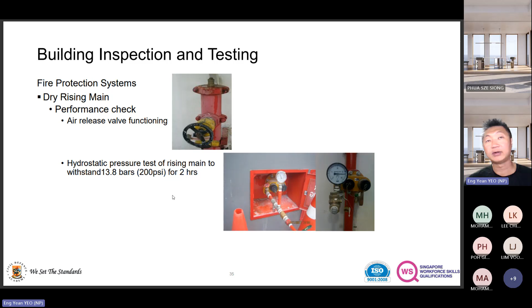Now the wet riser, and all the wordings. We usually don't label in such a manner. We don't use WR, so we always put things like 1-5, 1-3. The breaching inlet must be mentioned, because it is important: they add more water supply and more flow rate into the system.